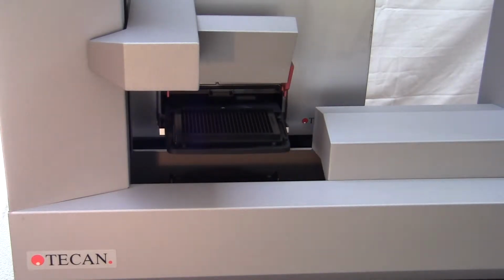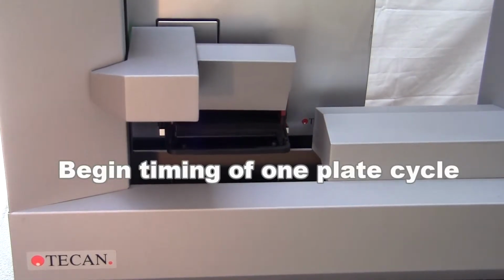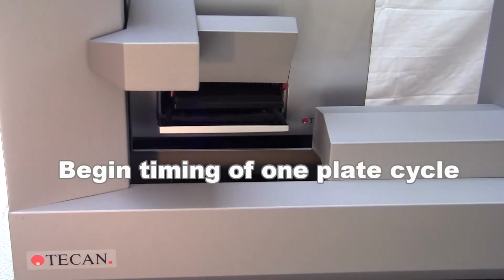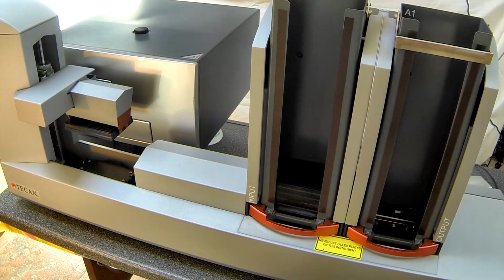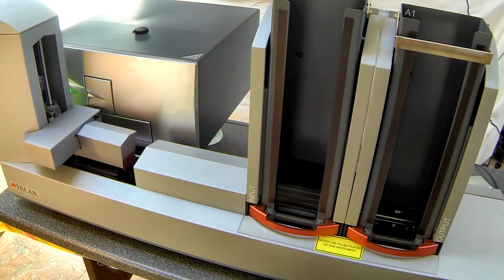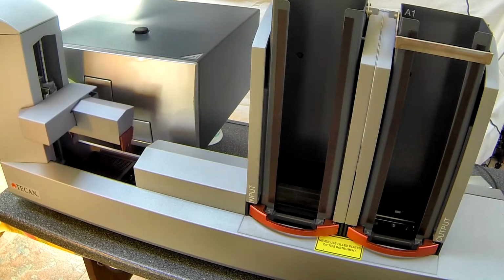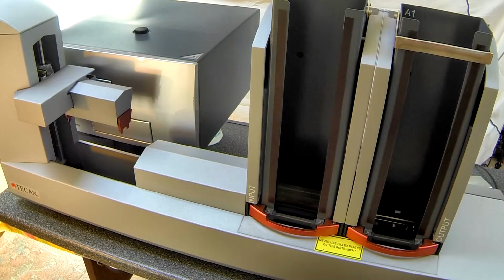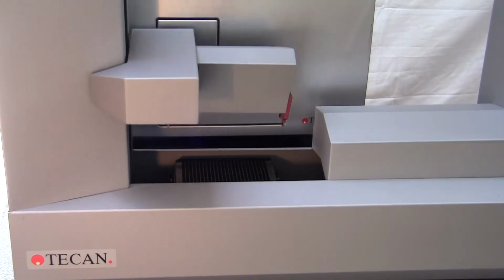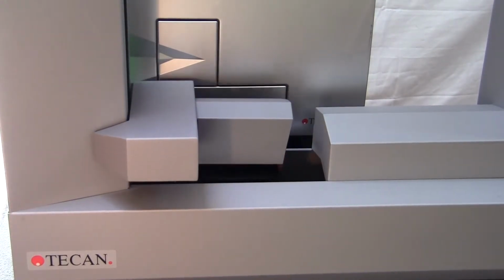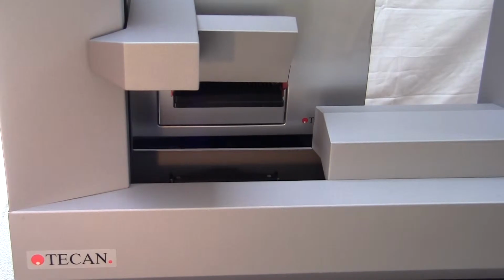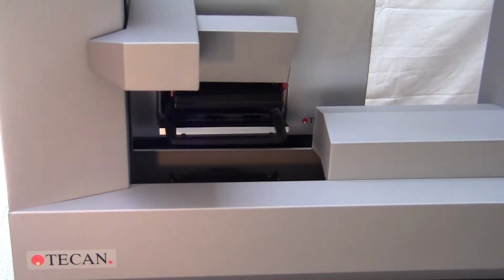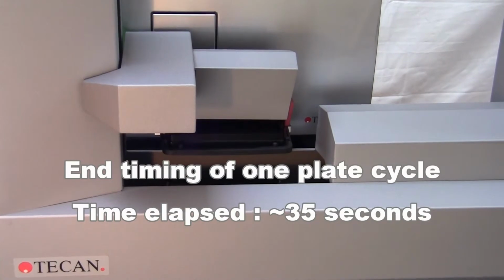So if you're interested in knowing what the cycle time is per plate for the CONNECT, here's an example of what that looks like. From the point it deposits one plate, returns it to the output stack, picks up another, and sets it back in the plate carrier, that time is approximately 35 seconds.